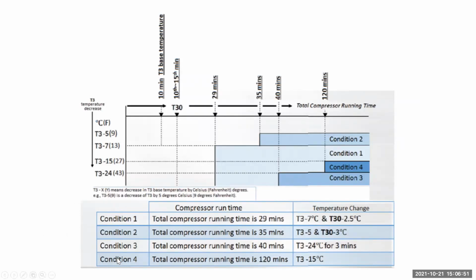This has 4 conditions on it to when it'll go into defrost. There's now 5. When the compressor reaches a total cumulative runtime of 120 minutes, that's when it will go into defrost, as long as the T3 sensor is reading the correct temperatures.